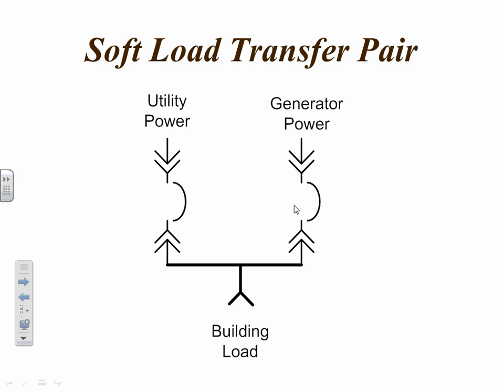We close that breaker. We're now supplying the building load along with the utility. So the store is running along. It hasn't seen anything happen because all we've done is close this breaker, but it's in sync. Now we open this breaker and we're still supplying power to the load by the generator. The load doesn't know anything happened. It's a great system. The utility says, okay, we're going to run it for about 6 hours.